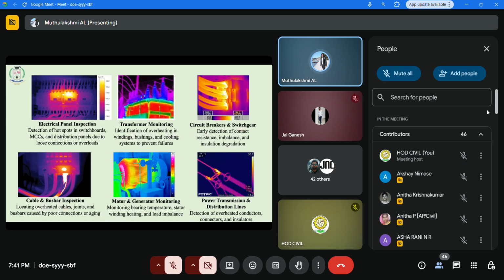Likewise, transformer monitoring, circuit breaker and switch gear, cable and bus bar inspection - bus bar inspection is very important because it collects power and distributes it to other circuits, so it should be analyzed, monitored, and inspected through infrared camera.